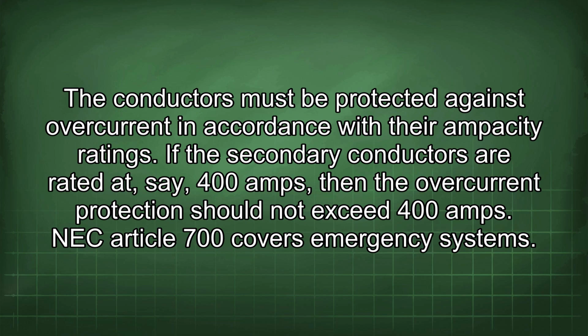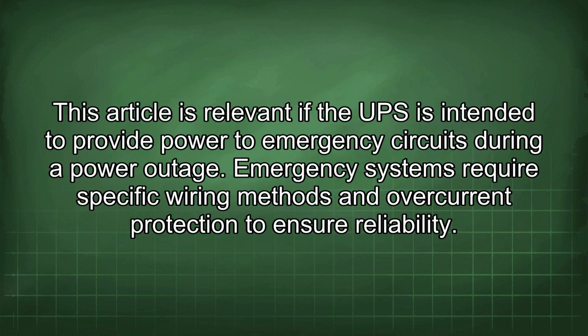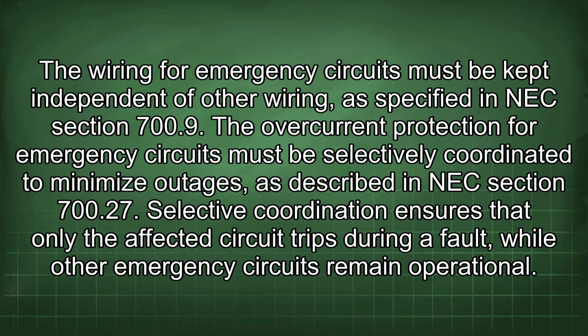NEC Article 700 covers emergency systems. This article is relevant if the UPS is intended to provide power to emergency circuits during a power outage. Emergency systems require specific wiring methods and overcurrent protection to ensure reliability. The wiring for emergency circuits must be kept independent of other wiring, as specified in NEC section 700.9.